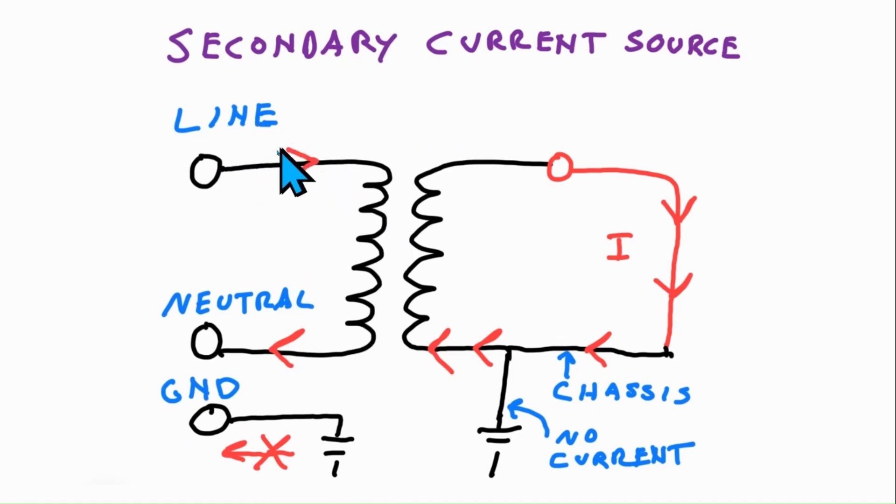So the current through line and the current through neutral still is the same, even though we have current flowing into the chassis and then back into the secondary source of current. So that's how you're able to pass current through the chassis and grounded chassis without tripping the GFCI.